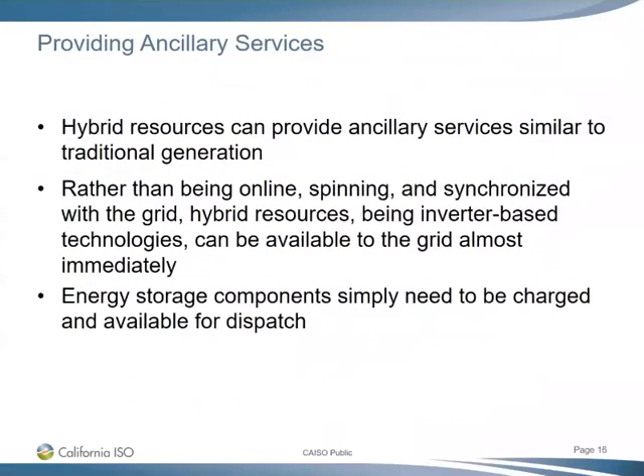Providing ancillary services is another driver. These resources could provide ancillary services similarly to traditional generation. Examples already exist of combinations of storage and gas resources online that provide ancillary services in an improved manner compared to standalone resources. When storage is added to hybrid resources, a traditional generator doesn't need to be online spinning or synchronized — since they are inverter-based, they can be available to the grid almost immediately. Storage just needs to be charged and ready for dispatch to provide those ancillary services.